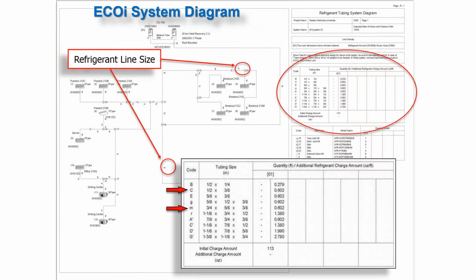Okay, Panasonic provides us, Wallace Ennis, with a system called the Pack Design System. It's a design software that allows us to do system layouts for design, sizing, engineering, all the work on the front end to make sure that we're meeting a building or a customer's needs with our Panasonic VRF. We can map out piping and wiring, and we can offer schematic layouts. Basically, what we see here is all of our line sizes, so there'll be a letter associated wherever it is on the schematic. It'll tell us our liquid and suction line, or if we're doing a heat recovery system, we'll have liquid, suction, discharge. We'll have 3 pipes.